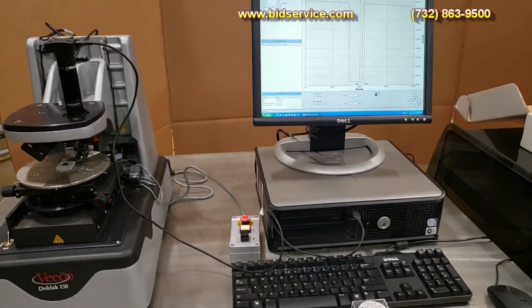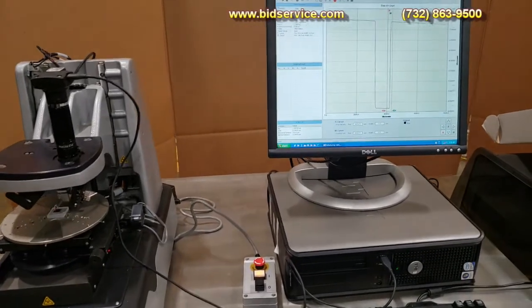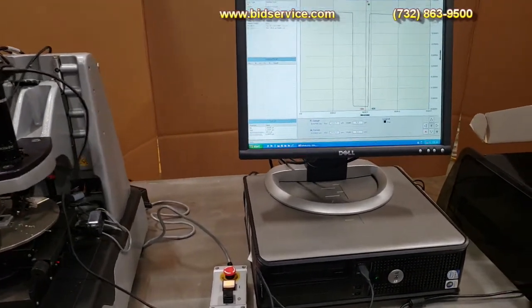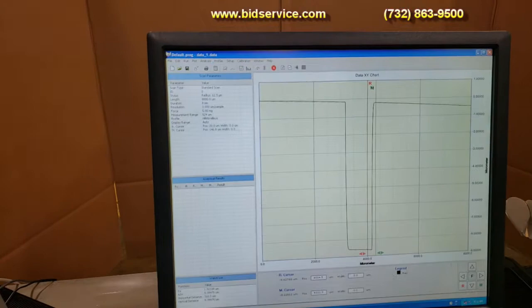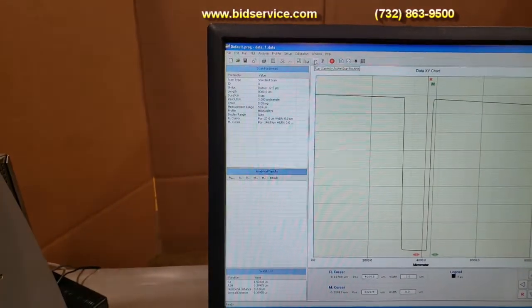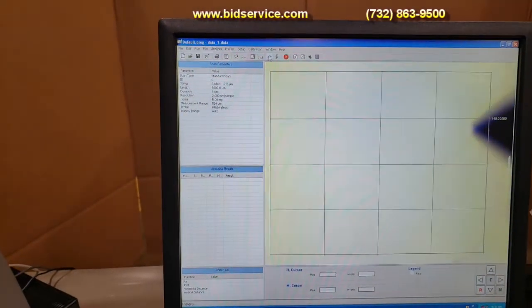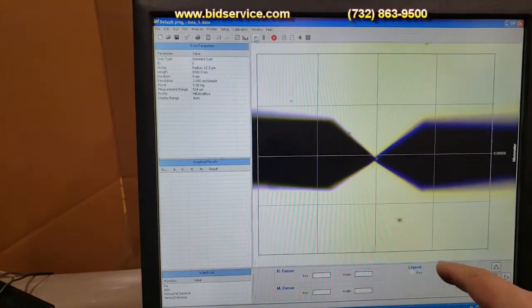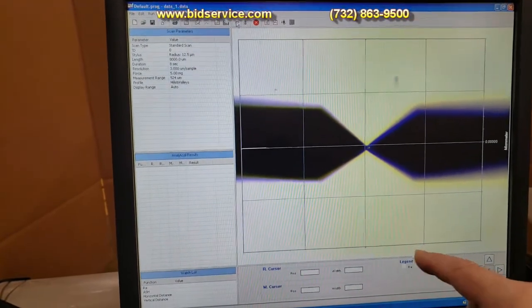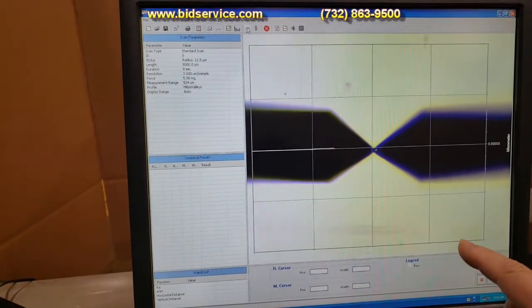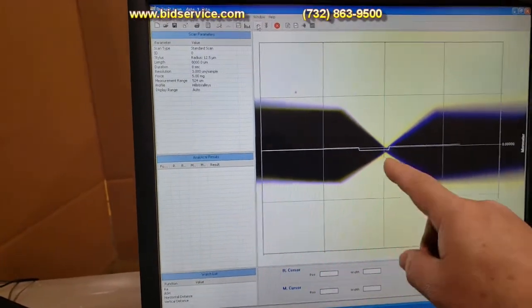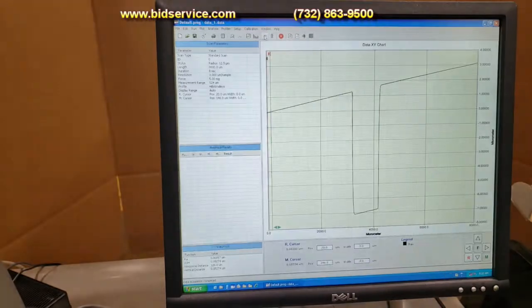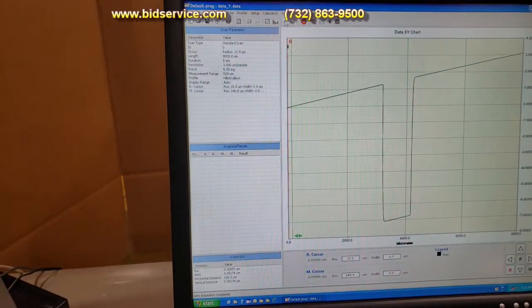So I put the other calibration standard in and I leveled it, as you can see, but I'm going to try to do it one more time and make it scan. As you can see, it is bringing the tower down, leveling it, and now it's getting ready to do the scan. This is the 8 micrometer standard. As you see, it went through the valley, right there. And here is your display.